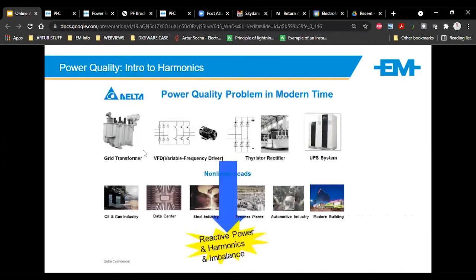So what causes these? Variable speed drives, thyristor rectifiers, UPSs, all these contribute to harmonic content within your network. It's what we refer to as nonlinear loads, and they're typically seen in data centers, process plants, automotive, modern buildings. They create reactive power issues, they create harmonics, and they can create imbalances on your network.